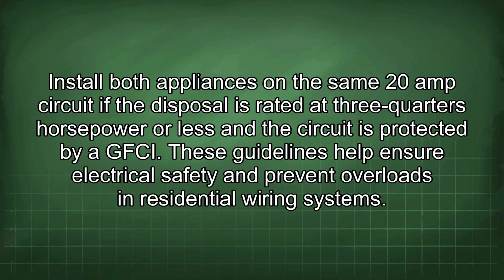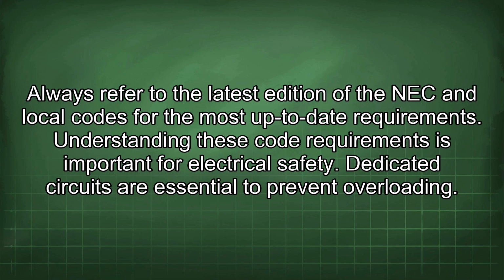Install both appliances on the same 20-amp circuit if the disposal is rated at 3/4 horsepower or less and the circuit is protected by a GFCI. These guidelines help ensure electrical safety and prevent overloads in residential wiring systems. Always refer to the latest edition of the NEC and local codes for the most up-to-date requirements. Understanding these code requirements is important for electrical safety.